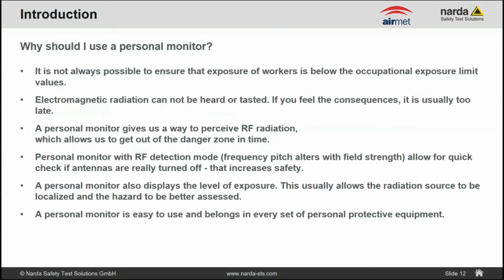Why should someone use a personal monitor? It's not always possible to ensure that the exposure of workers is below the occupational exposure limit values. The electromagnetic radiation cannot be felt or heard or tasted. If you feel the consequence, it's usually too late. So first effects of temporary blindness, for example. And the personal monitor gives us a way to perceive the RF radiation, to display it, to measure it, and which allows us to get out of the danger zone well in time.